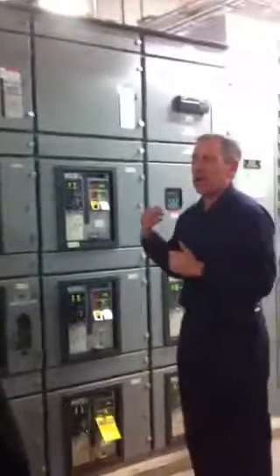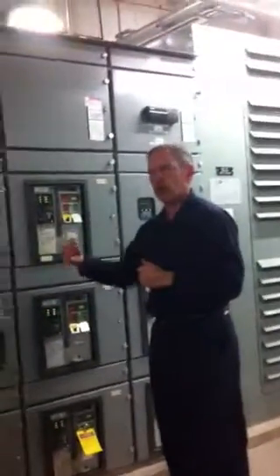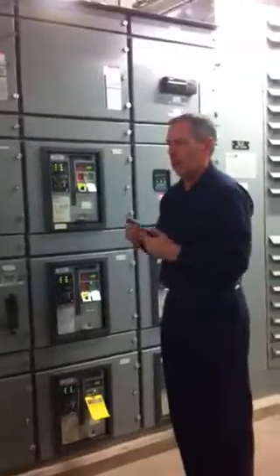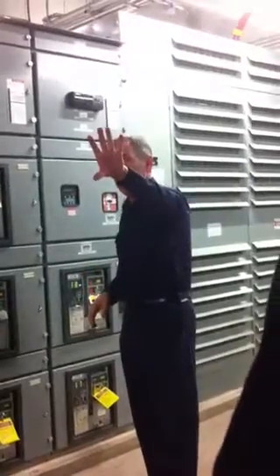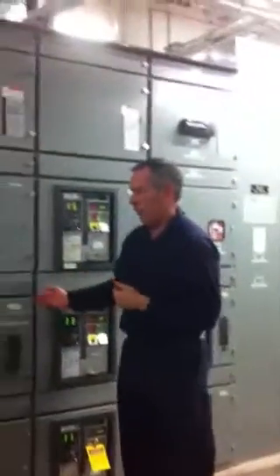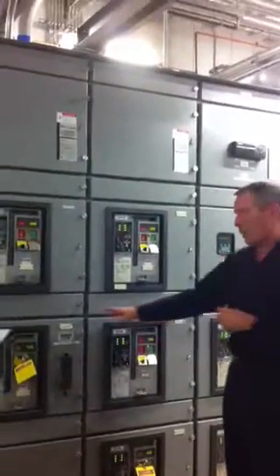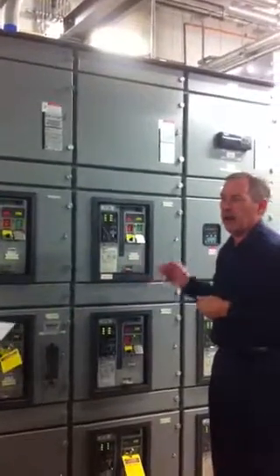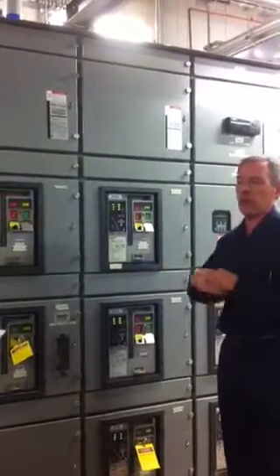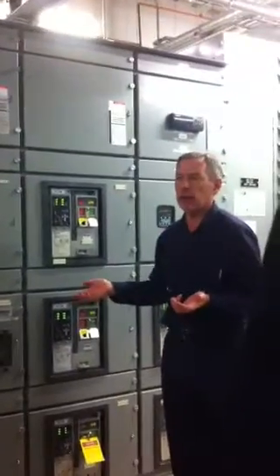Stephen mentioned the main tie main. In these facilities, we can actually isolate a transformer and energize, so you do not see a power outage in the building when we are doing that. We do that by making sure the transformers are the same size, the same impedance, fed off of the same front end gear, and then we are phasing the three phases coming into the tie breaker exactly the same. You don't want to feed one board with different phasing. All of your motors on that side would turn backwards, anti-clockwise or clockwise.